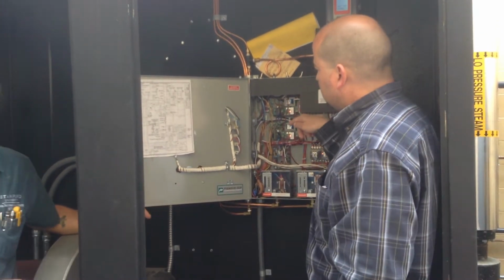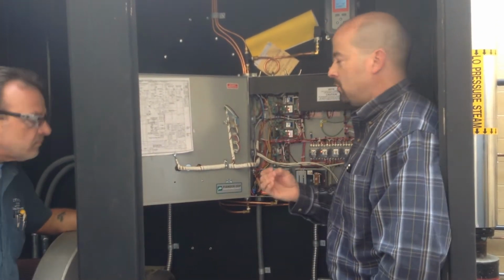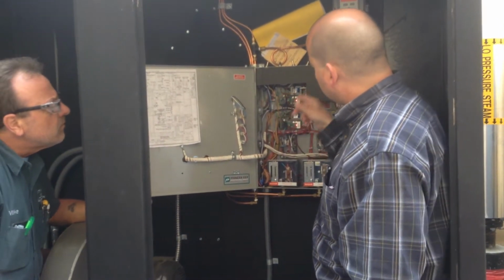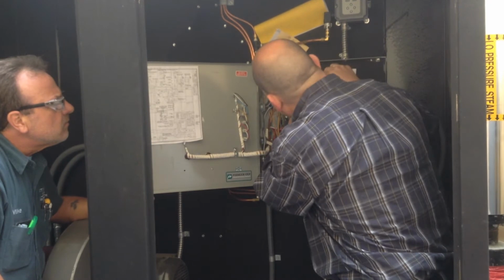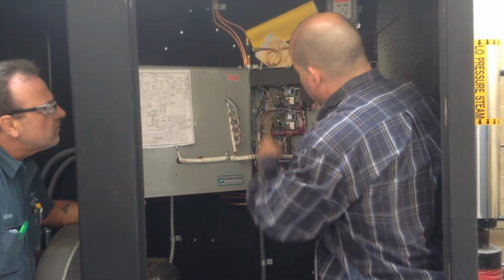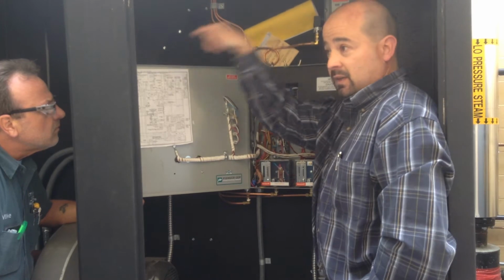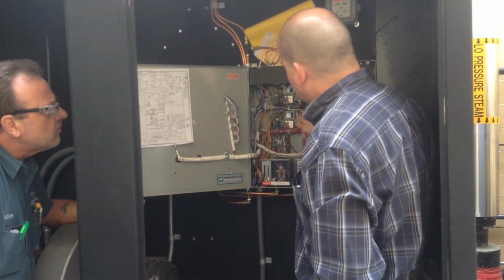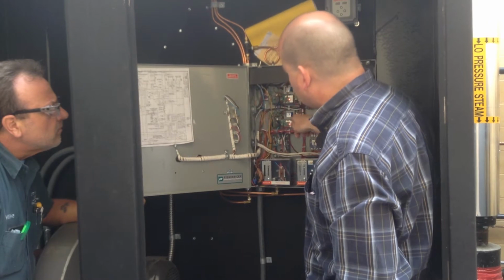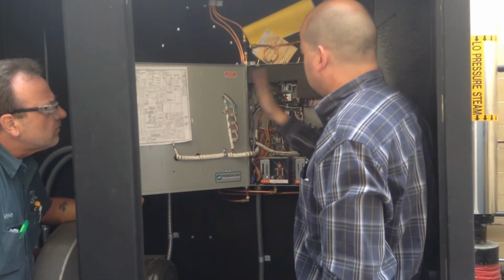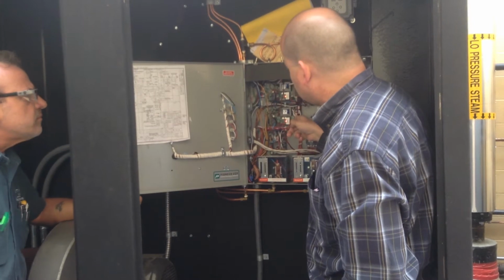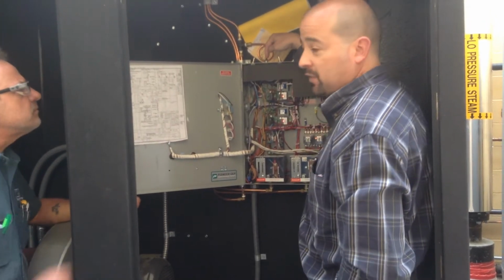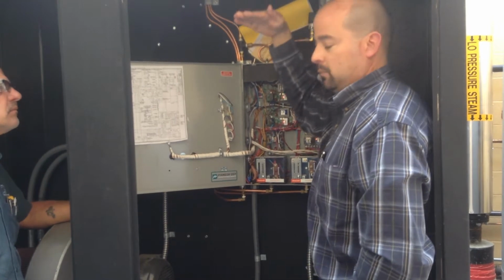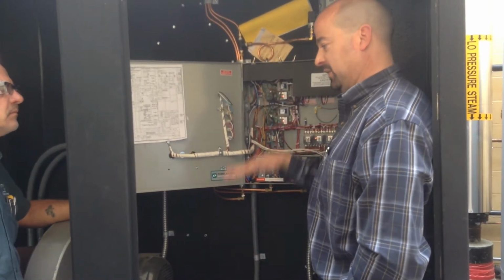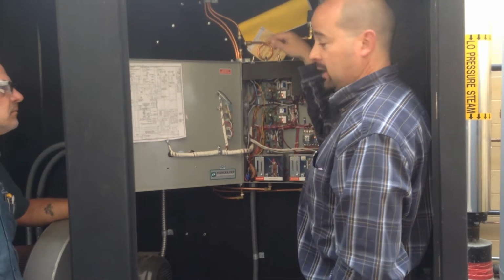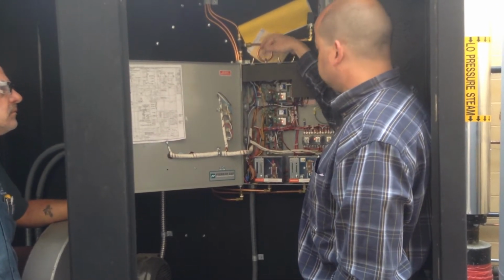These two circuit boards here are what we call dual function controls. There's a label and a sticker for what they do. So this one, for example, is low water. That's your low water control, the automatic reset, the one that's in the water column. The secondary low water is on this side right here. So if you cut this control in half, it does two things. This one, secondary low water, has a manual reset button, which is right here. If the water level in the boiler were to get below the second probe, this one would trip, and the boiler would not fire unless you manually reset this.